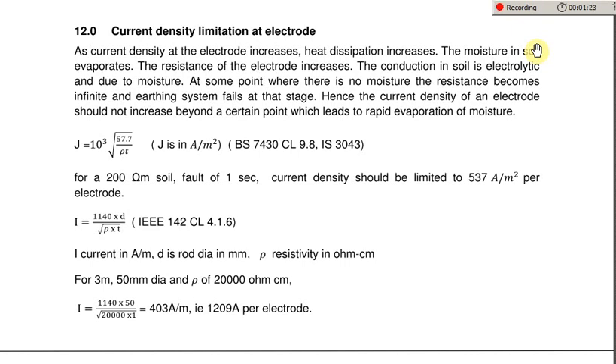We call this as failure of the earthing electrode or the earthing system, and we should prevent this from happening. In order to prevent this failure of the earthing electrode, the current density in a particular electrode should not increase beyond certain levels. This is the formula for this current density.